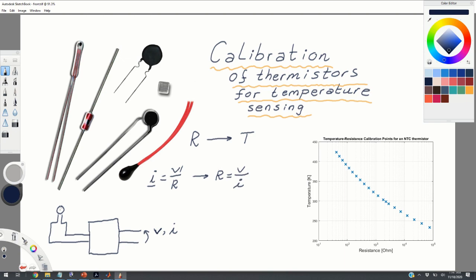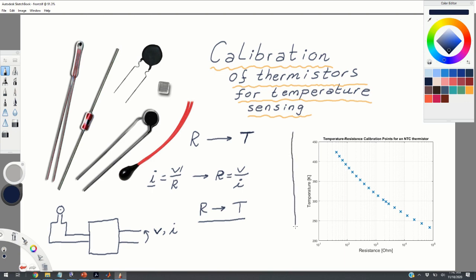Now, if the temperature in the room, in your lab environment, or on your device changes, you will observe the change of the resistance. The goal is to convert this value of resistance into temperature. To convert the resistance into temperature, you need to know some mathematical relation or a graph that relates resistance with temperature. The first thing you should do is look into the specs of your thermistor and try to obtain the so-called calibration curve or calibration data points.